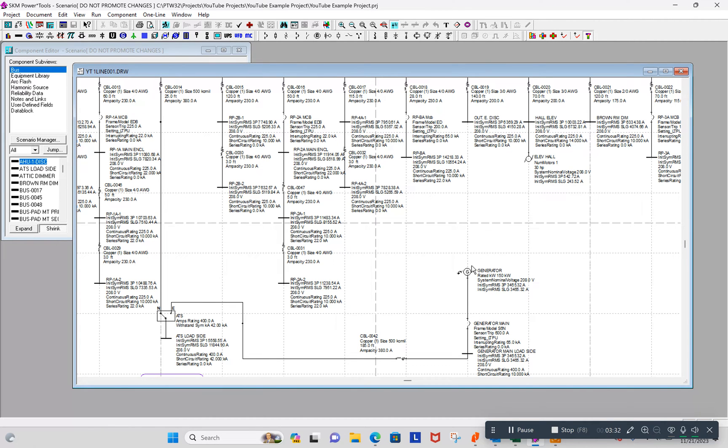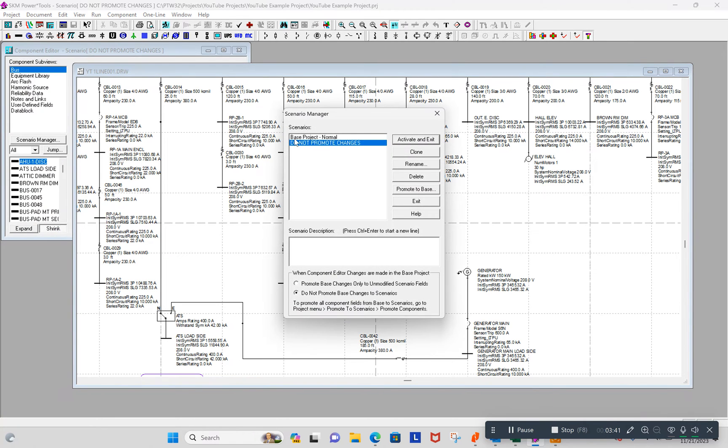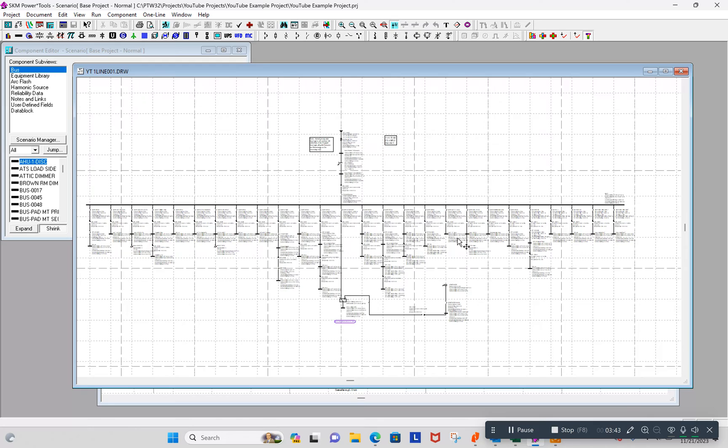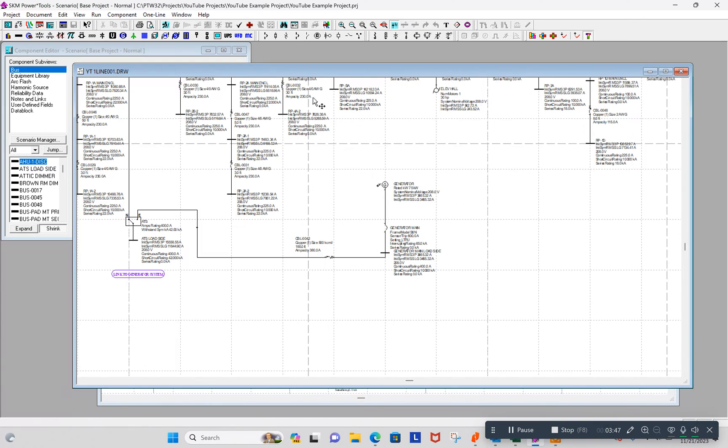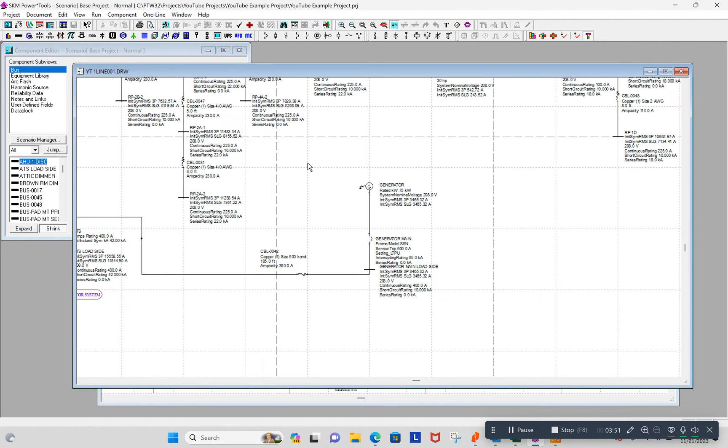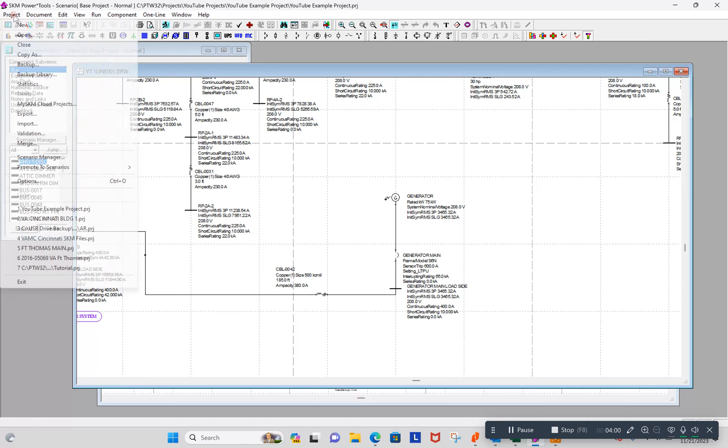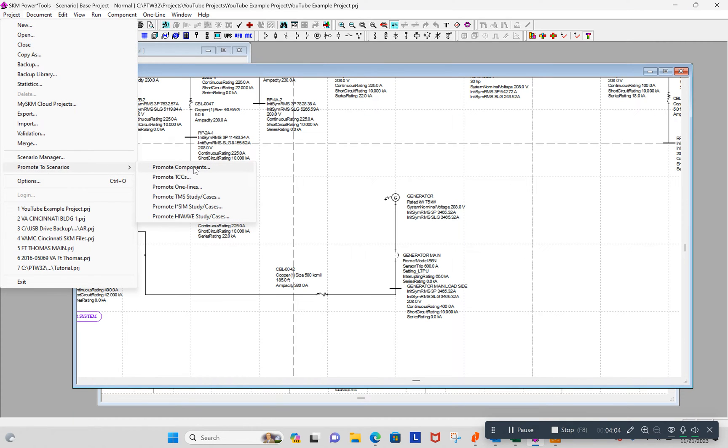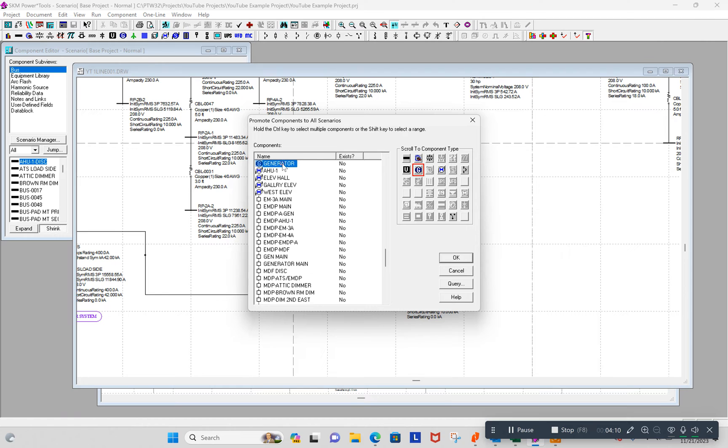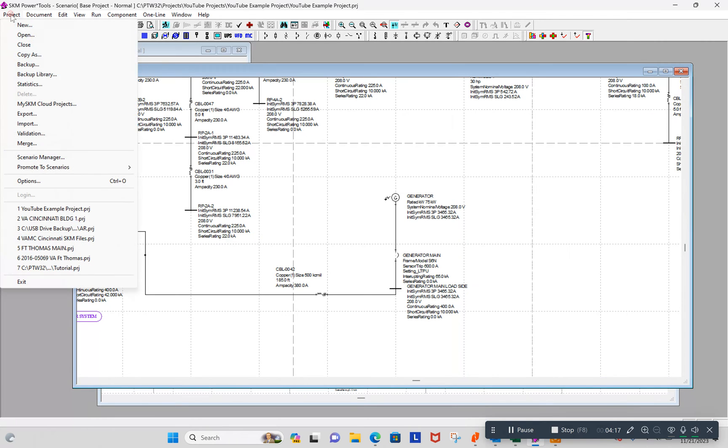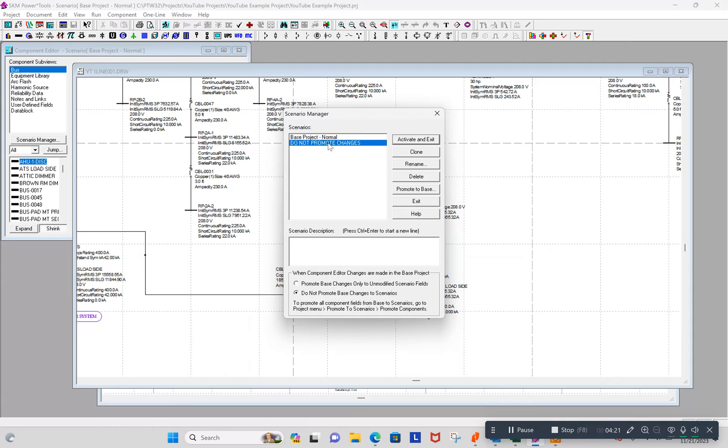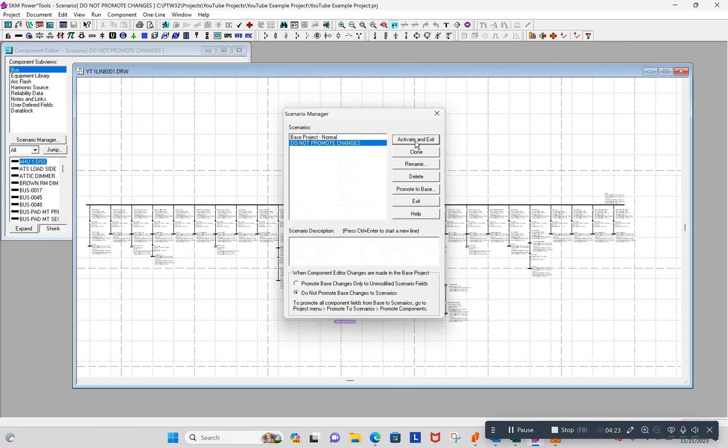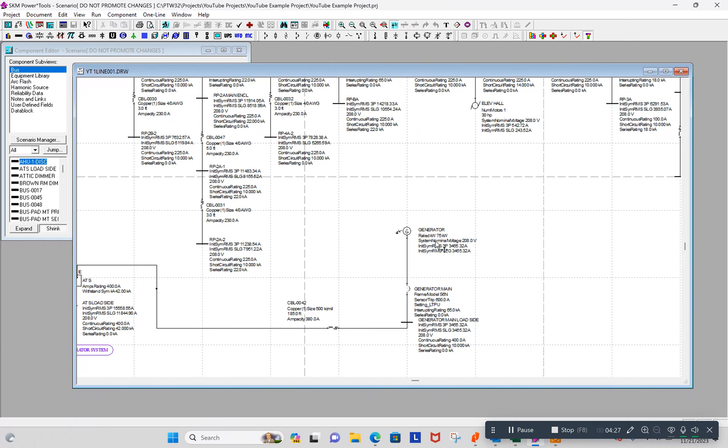So what if I decide, oh, I do want to change, promote the change from the base to all the scenarios. Let's go back to the base scenario. And I decided, well shucks, I've made all these different changes here, and I wish I would have had those automatically put into the scenarios so I don't have to go in and possibly make a mistake changing them one by one. So then you can go back to project, promote scenarios, promote components, and I'm going to change the generator. I'm going to hit OK. Now when I go to that do not promote changes scenario, it should be changed to 75 from 150, and it is.